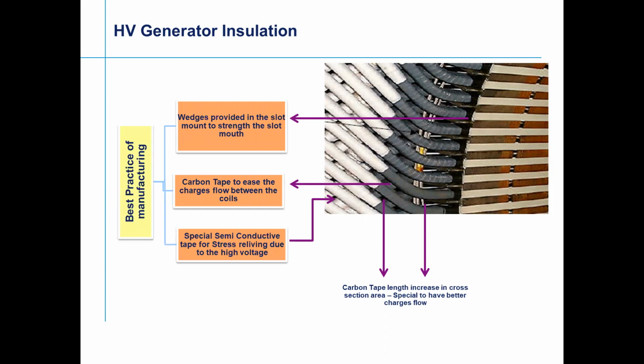So this is a slot edge after the winding. We put the wedge over here, you can see this. And there is a carbon tape which is put across to discharge the flow of charges on the slot mouth, and a separate semiconductor tape is stretched over that. In case of any high voltage, there is a movement of the coil due to the electromagnetic force. So this is put across as a part of extra insulation on the HT coils. And of course, after the carbon tapes have been given, this goes for the VPI process for the HV generator insulation. So the HV generator insulation scheme is altogether different from an LV generator.